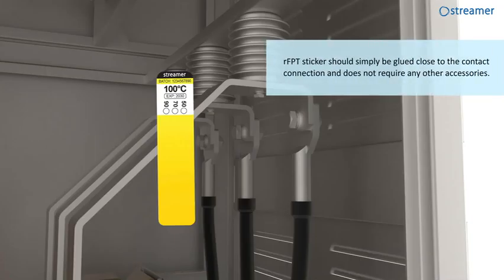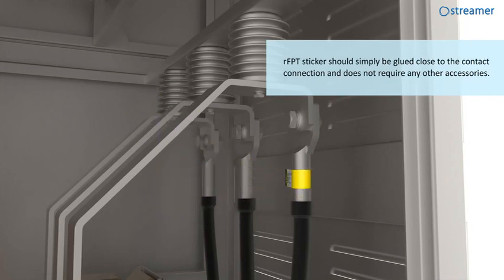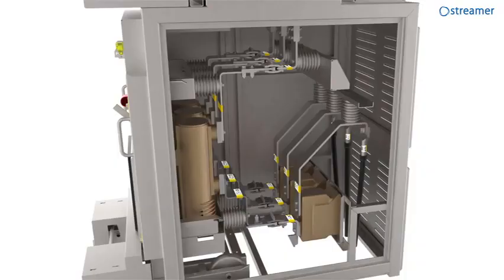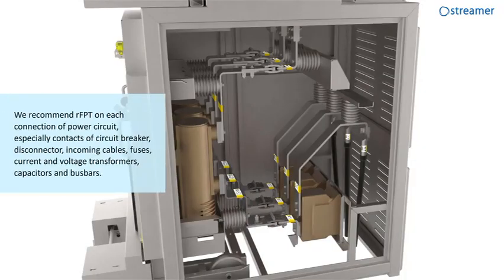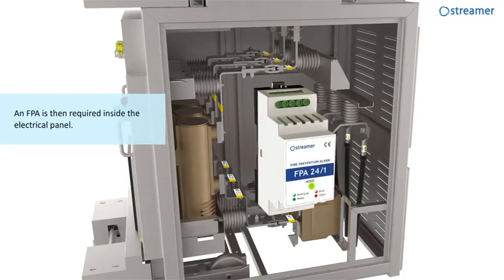RFPT sticker should be simply glued close to the contact connection. It doesn't require additional accessories to install and is very convenient to use. We recommend RFPT on each connection of power circuit, especially contacts of circuit breakers, disconnectors, incoming cables, fuses, current and voltage transformers, capacitors, and bus bars. An FPA is then required inside the electrical panel.